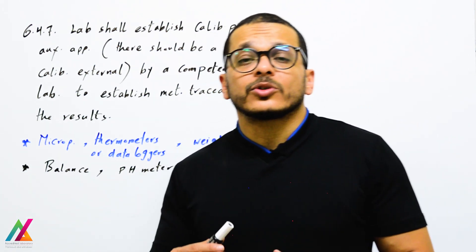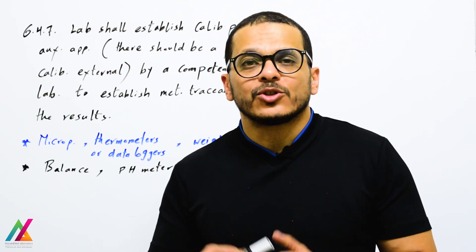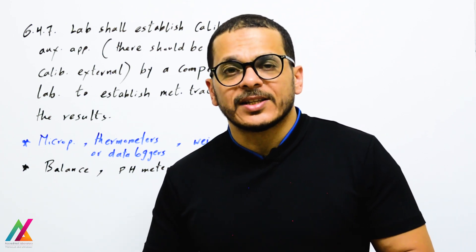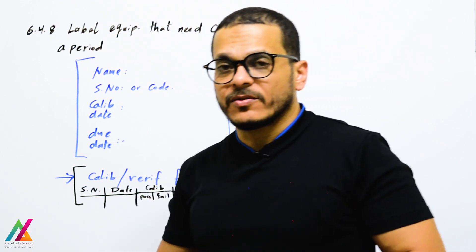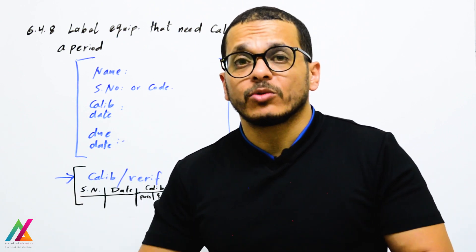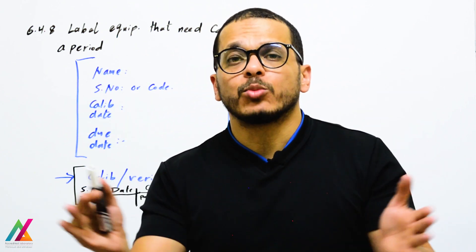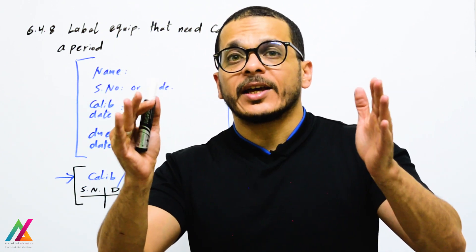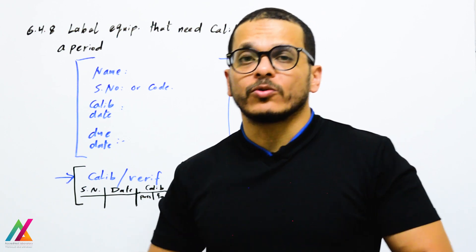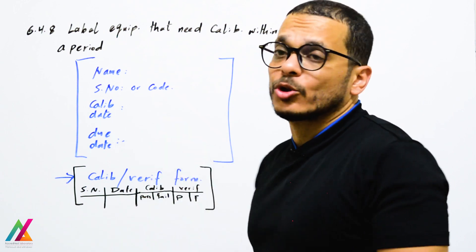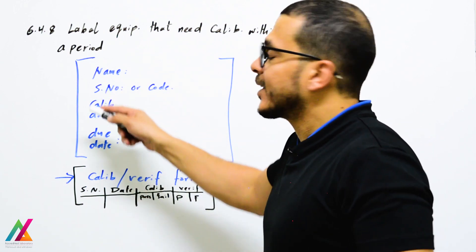A balance is calibrated internally using calibrated weights, and a pH meter is calibrated using buffers. Other instruments used for measurement of target analytes shall be calibrated before use to ensure valid results. Equipment requiring calibration within a specific period shall be labeled to prevent misuse after the calibration due date. Labels should include the instrument name, serial number or code, calibration date, and due date.